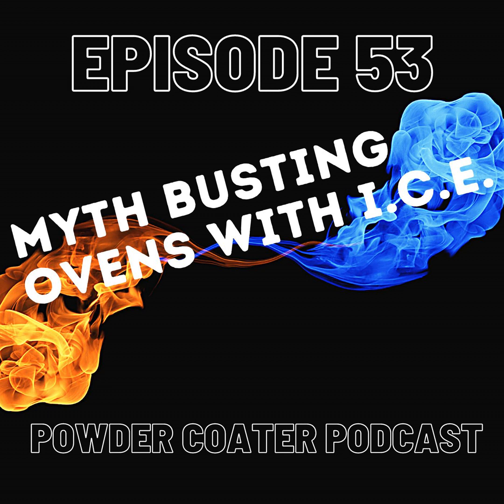For powder, you just have what's required for a turnover rate. What we do in all our ovens is put all of the exhausters on VFDs, variable frequency drives, so I can change the volume. Typically we'll set that exhaust up to maintain a slight negative in the oven, so I'm holding the hot air in, but I'm not pulling a lot of cold air in. And of course, with powder, we don't really have any nasties or VOCs that we have to worry about. So the exhaust is balanced out.